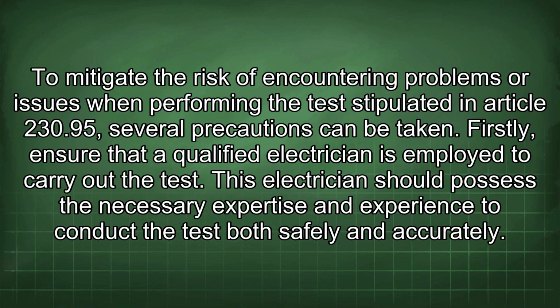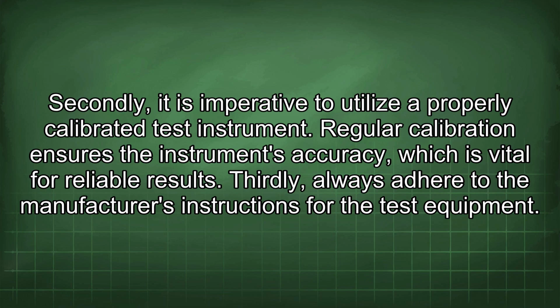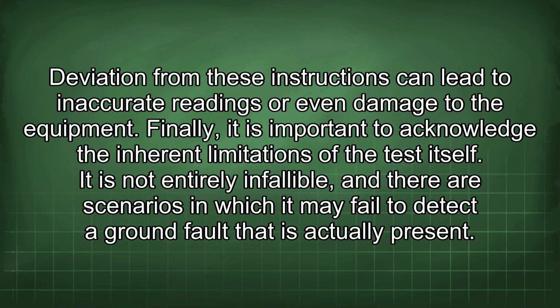To mitigate the risk of encountering problems or issues when performing the test stipulated in Article 230.95, several precautions can be taken. Firstly, ensure that a qualified electrician is employed to carry out the test. This electrician should possess the necessary expertise and experience to conduct the test both safely and accurately. Secondly, it is imperative to utilize a properly calibrated test instrument. Regular calibration ensures the instrument's accuracy, which is vital for reliable results. Thirdly, always adhere to the manufacturer's instructions for the test equipment. Deviation from these instructions can lead to inaccurate readings or even damage to the equipment. Finally, it is important to acknowledge the inherent limitations of the test itself. It is not entirely infallible, and there are scenarios in which it may fail to detect a ground fault that is actually present.